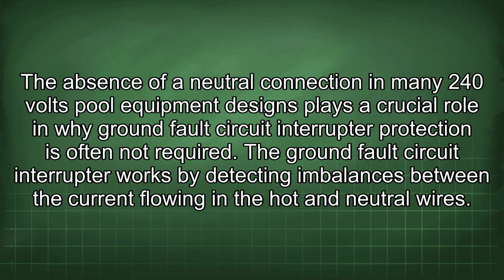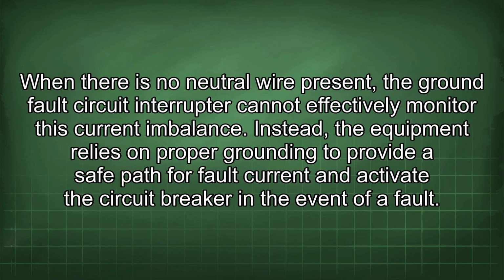The absence of a neutral connection in many 240 volt pool equipment designs plays a crucial role in why ground fault circuit interrupter protection is often not required. The ground fault circuit interrupter works by detecting imbalances between the current flowing in the hot and neutral wires. When there is no neutral wire present, the ground fault circuit interrupter cannot effectively monitor this current imbalance. Instead, the equipment relies on proper grounding to provide a safe path for fault current and activate the circuit breaker in the event of a fault.